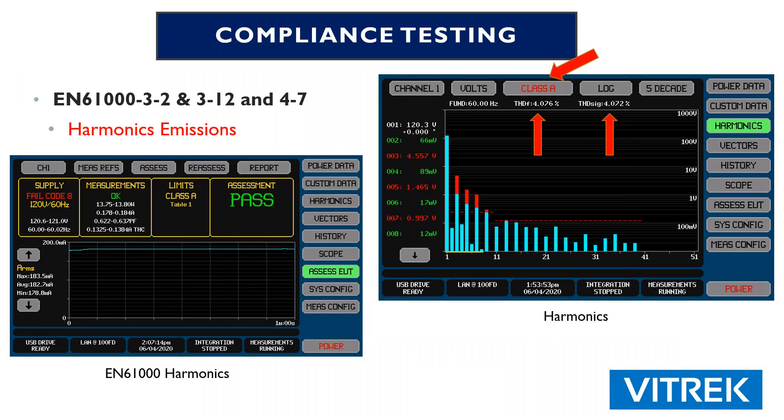Another test that becomes important is harmonics, which is mentioned in both the LM79-19 and the ANSI document. They talk about harmonic emissions. The screen on the left is a capability built into the Vitrek PA900 series power analyzers, where we've got the ability to measure to those specific EN61000 specs. You'll notice the screen on the right shows different classes — class A, class B, C, D, etc. On our harmonic screen, we're giving you right there on the screen the total harmonic distortion for both the fundamental and the whole signal.